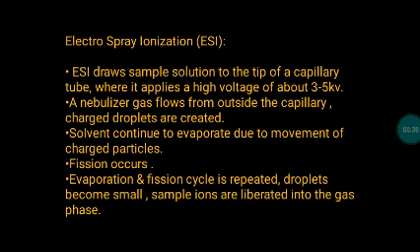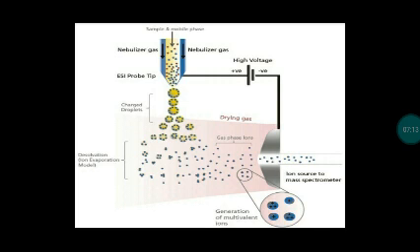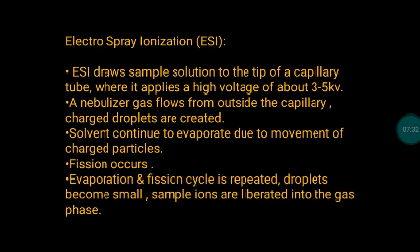ESI draws the sample solution to the tip of a capillary tube where it applies a high voltage of about 3 to 5 kilovolts. It is a type of evaporative ionization technique. A nebulizer gas flows from outside the capillary and charged droplets are created. Through the capillary, sample is injected and at the tip of the capillary high voltage is applied, spreading the sample due to the presence of nebulizer gas, creating charged droplets.